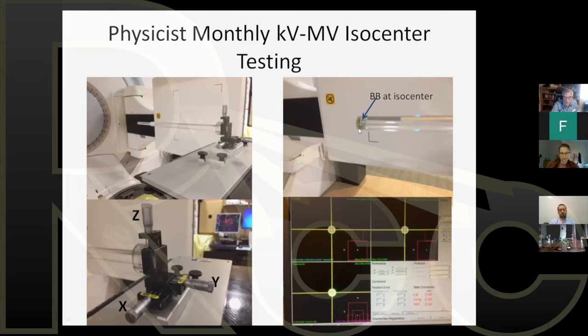So you set up your lasers at this ball bearing, and then you image it. 2 images at each cardinal angle. So that's 8 images altogether. And then a software program within the Elekta package, within FlexMap, there's a software program that will find that BB in the center of the radiation field. So you'll see a radiation field and a dense BB in the middle of it. And the program analyzes where that BB is within each radiation field and then calculates how far off the center is from the center of the field.